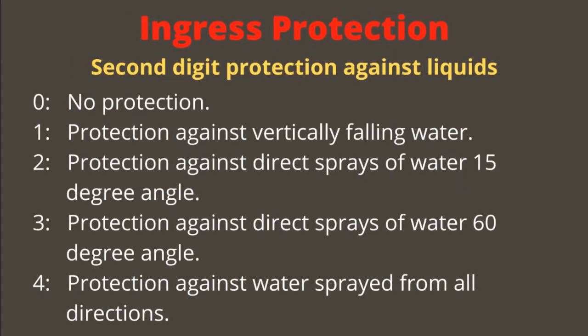6 is complete protection from dust. The second digit of IP — protection against liquids: 0 is no protection; 1 is protection against direct falling water; 2 is protection against spraying water at a 15-degree angle from the vertical.